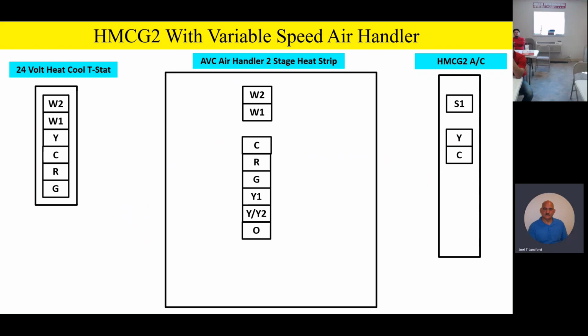On a variable speed air handler or variable speed furnace, you're going to have a dip switch on there that's going to say heat pump or AC. Make sure you flip that little switch that says AC. That way it ignores the O signal, okay? And so remember, the O signal is an important part on the heat pump if you're hooked up to a heat pump, but on a straight cooling product, the variable speed product inside does not have to have an O signal.